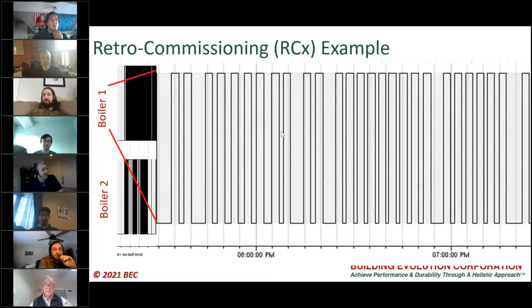So why is it doing that? We looked into different possible problems, and one issue was with the pumping — 2 pumps, one failed, leaving just 1 pump for 3 buildings: north, east, and south, with south being the biggest. Two boilers, one pump, that's it — the boilers are primary only, with no pumps of their own. The system then breaks into 3 loops and comes back to the boilers, with a strange bypass trying to reduce pressure in the south building loop.